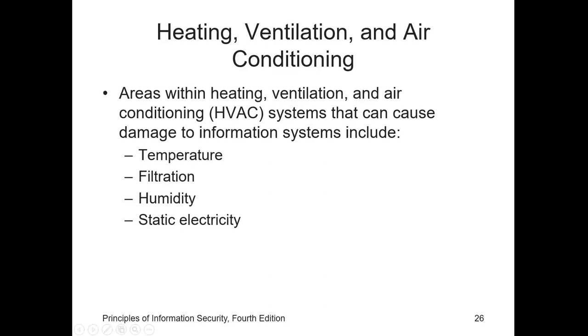There are two types of failures that can result from electrostatic discharge damage to chips. The first is immediate failure, also known as catastrophic failure, which occurs right away and is usually totally destructive. The second is latent or delayed failure that can occur weeks or even months after the damage is done. It's imperative to maintain the optimal level of humidity, which is between 40 and 60 percent in the computing environment. Humidity levels below this range create static and levels above create condensation.